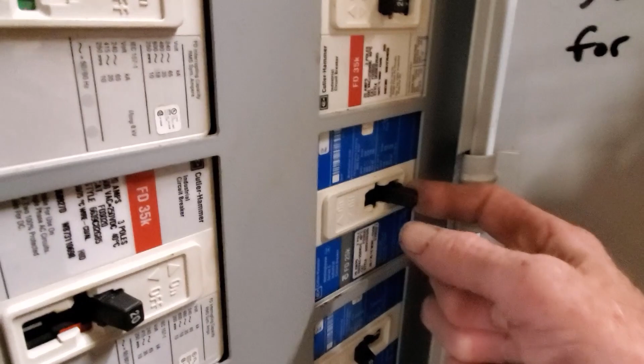Since those are off, I can go ahead and turn on the evap pump breaker. So the next two things that have to go on are the heat recovery pump, which is this guy right here, and the condenser water pump, which is that guy right there.